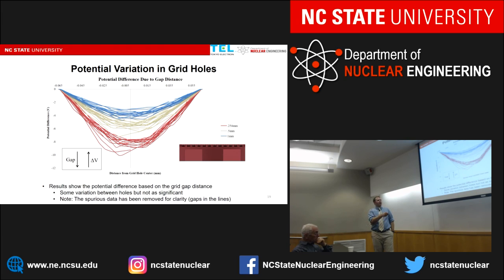And in this instance, just like that plot you saw earlier, we took the potential drop across each hole, but then we plotted it on top of itself. So that allows you to see the variation between each hole, but it also allows you to see the variation based on the grid gap distance. And what we find is, yes, there is variation between each hole, but the more consistent or important trend that we see is that with decreasing gap distance, we get an increasing potential difference in the grid holes, meaning that what we're applying to the grid is getting worse in the grid holes because it's not meeting the same potential that we're applying to the grid.